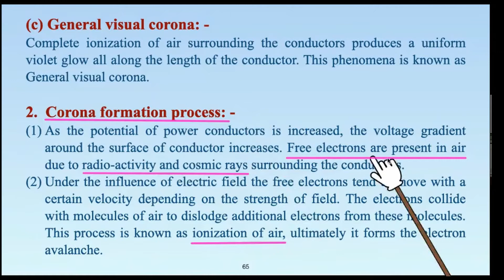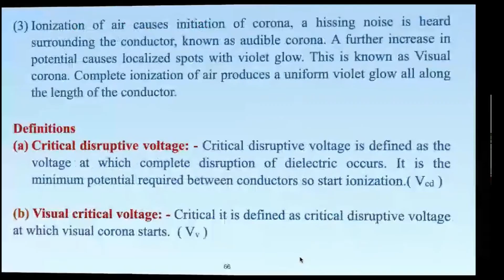So corona formation process: increase in voltage gradient, presence of free electrons, and ionization of air depending on the field strength. So these are the first two steps towards corona formation process. But yet it is only ionization. What is corona actually? A sustained electric discharge, as you defined. Let us move to the next slide.